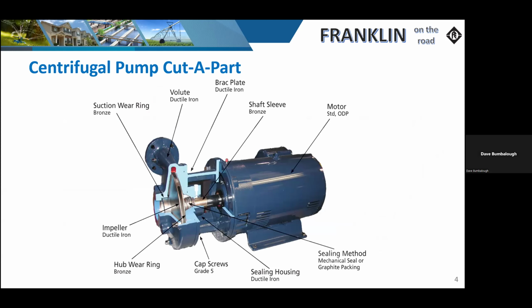So for the most part, I throw this centrifugal pump up here. It's an above ground pump. One of the issues that comes to my attention quite often is a new product being installed, and they hook it up. They start to use the system, and they notice it leaks between the pump and the motor. Well, that is due to this mechanical seal right in this general area right here.